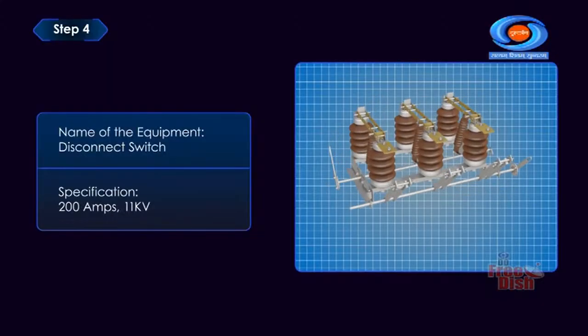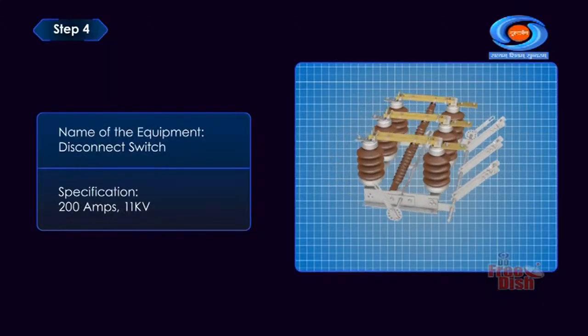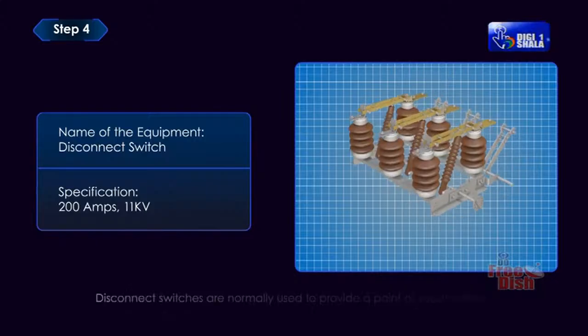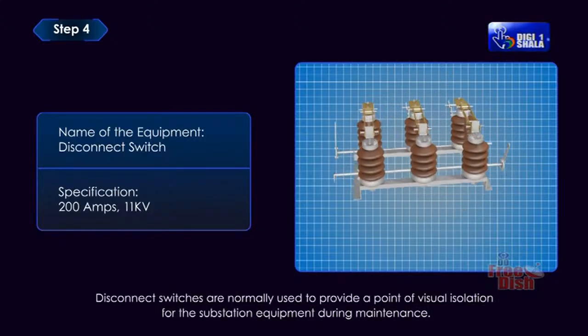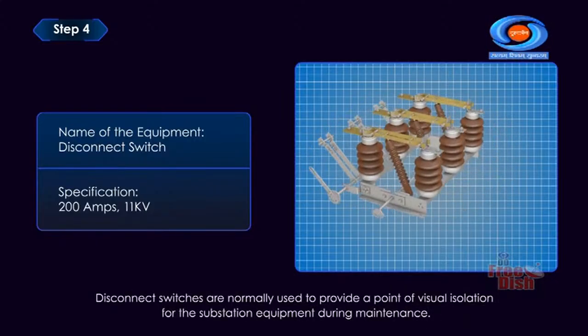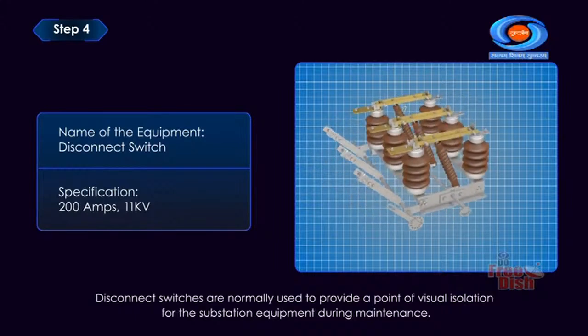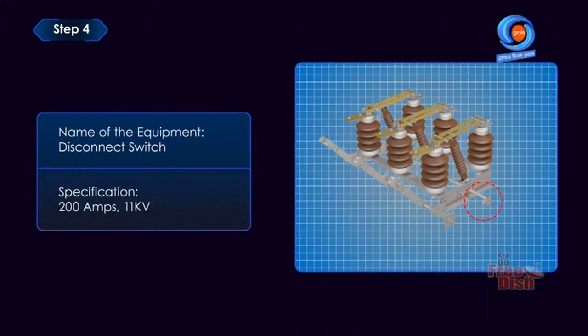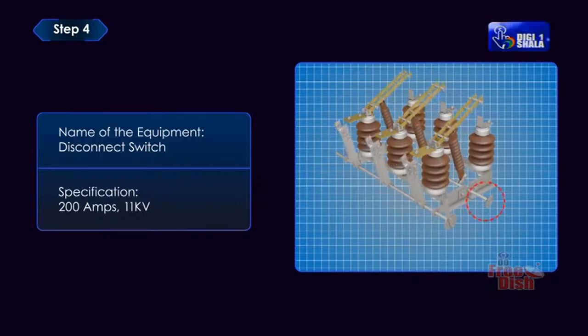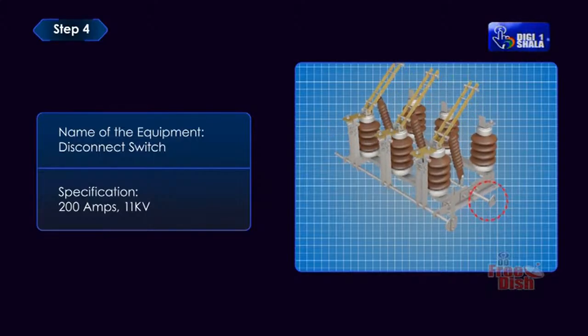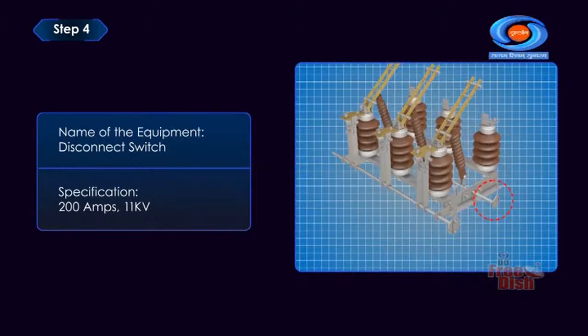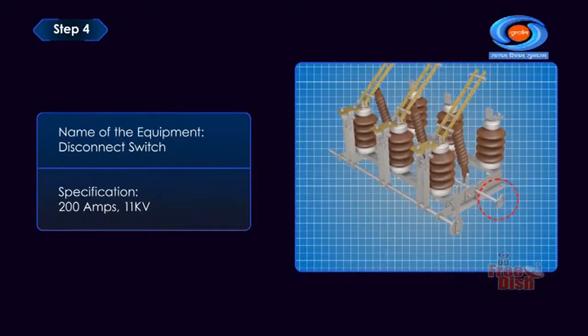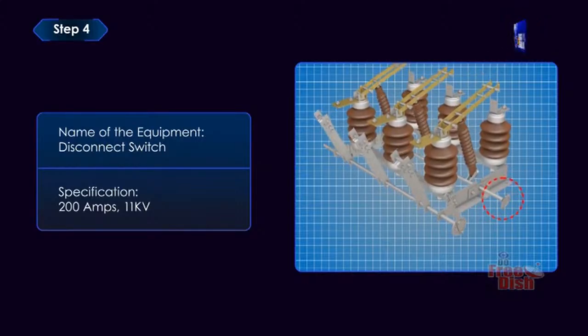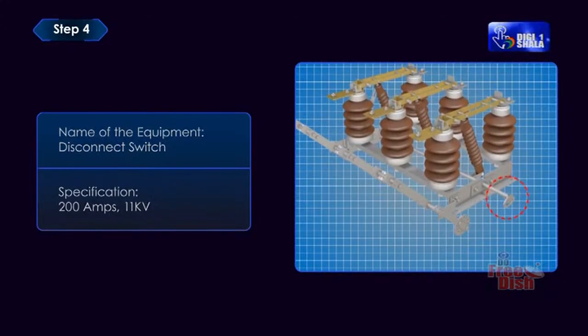Disconnect switch: 200 amperes, 11 kilovolts. Disconnect switches are normally used to provide a point of visual isolation for the substation equipment during maintenance. Typically, a disconnect switch would be installed on each side of a piece of substation equipment to provide visible confirmation that the power conductors have been opened for personal safety.